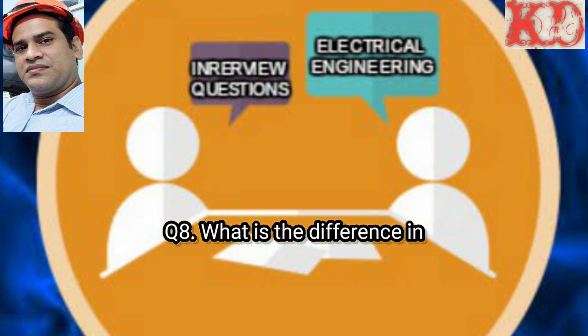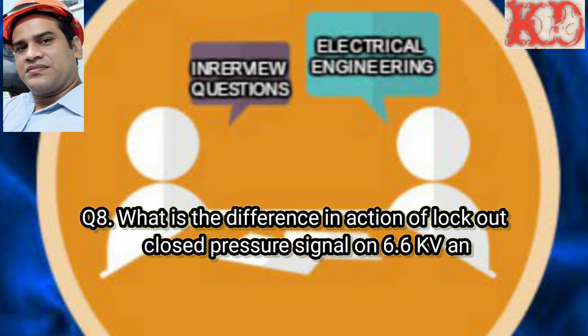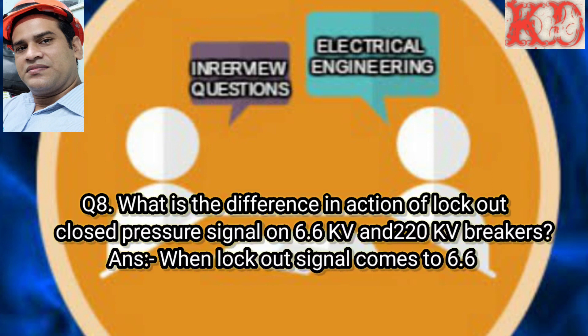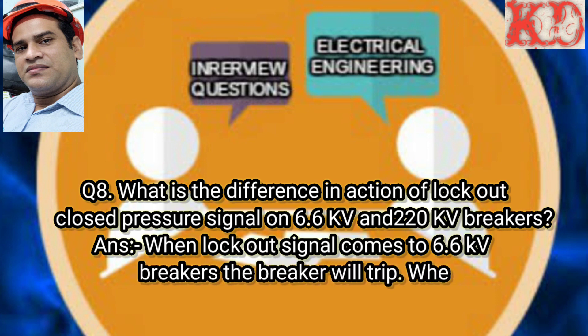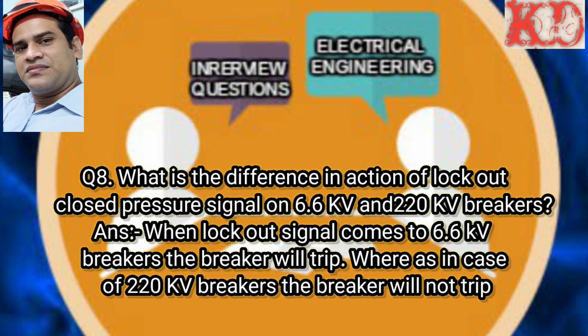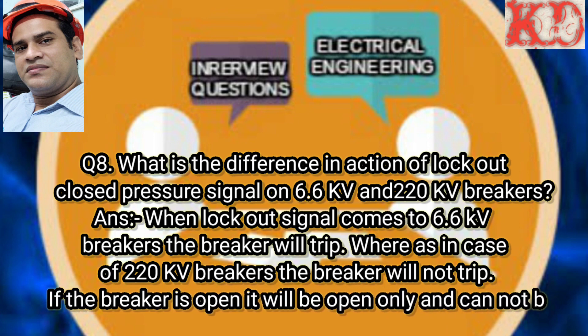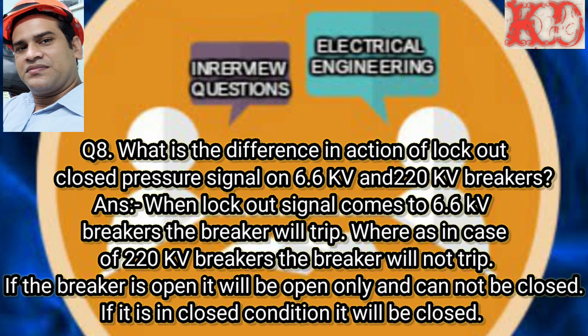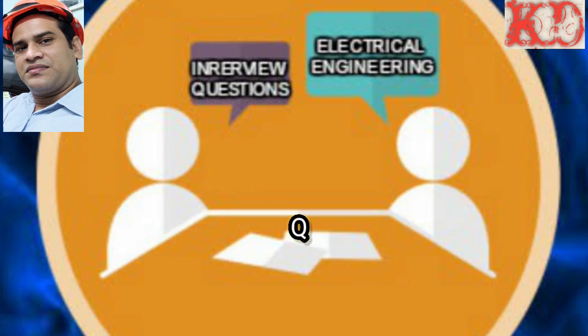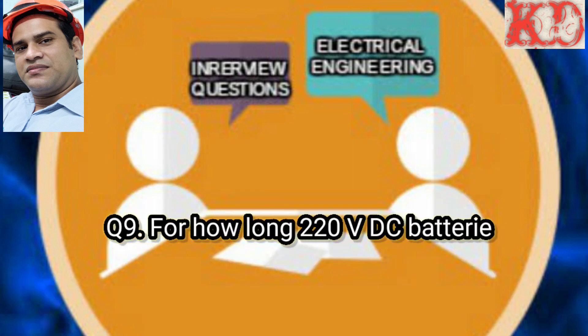Question number 8: What is the difference in action of a lockout pressure signal on 6.6 KV and 220 KV breakers? Answer: When a lockout signal comes to 6.6 KV breakers, the breakers will trip. Whereas in the case of 220 KV breakers, the breaker will not trip — if the breaker is open, it will remain open only, and if it is in closed condition, it will remain closed.